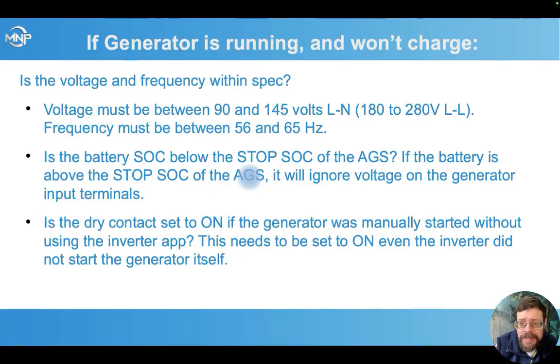If we've got our generator running and it won't charge the batteries, here's some common things to look at for why this is the situation. Look at, is the voltage and frequency of our generator within spec? We've got a pretty wide window we can operate from, but sometimes, especially some of the really cheap small generators, they may be bouncing outside of this window, even if just for a second or two, and it may not be connecting.